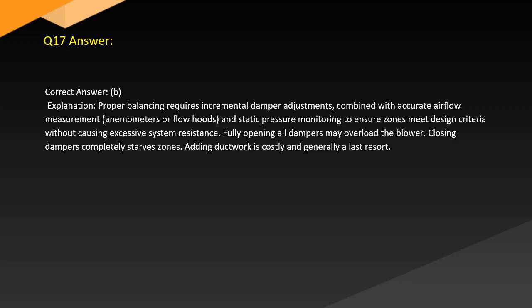Answer. Correct answer, B. Explanation. Proper balancing requires incremental damper adjustments combined with accurate airflow measurement, using anemometers or flow hoods, and static pressure monitoring to ensure zones meet design criteria without causing excessive system resistance. Fully opening all dampers may overload the blower. Closing dampers completely starves zones. Adding ductwork is costly and generally a last resort.